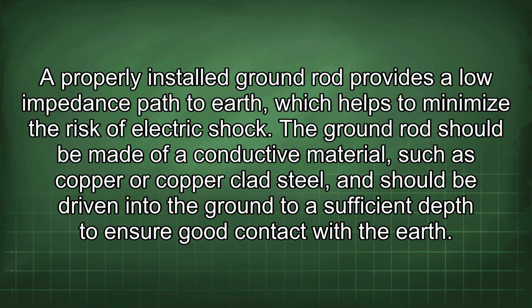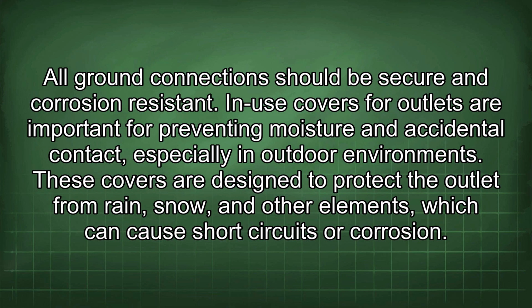A properly installed ground rod provides a low impedance path to earth, which helps to minimize the risk of electric shock. The ground rod should be made of a conductive material, such as copper or copper-clad steel, and should be driven into the ground to a sufficient depth to ensure good contact with the earth. All ground connections should be secure and corrosion-resistant. In-use covers for outlets are important for preventing moisture and accidental contact, especially in outdoor environments.